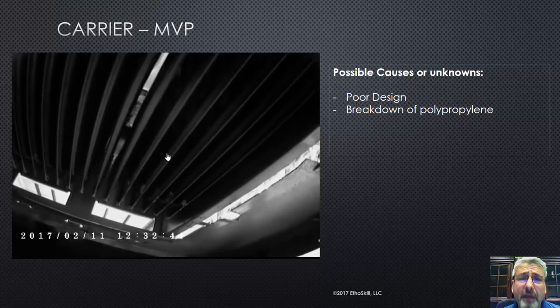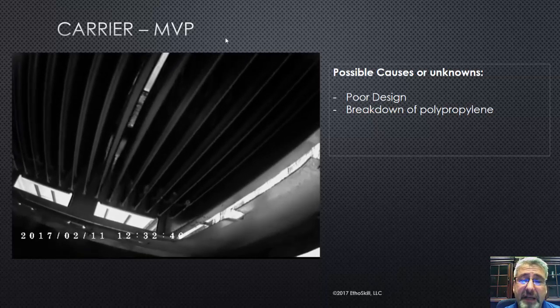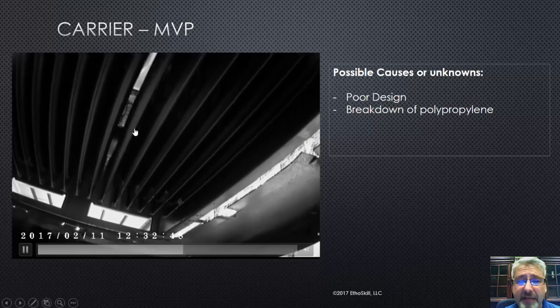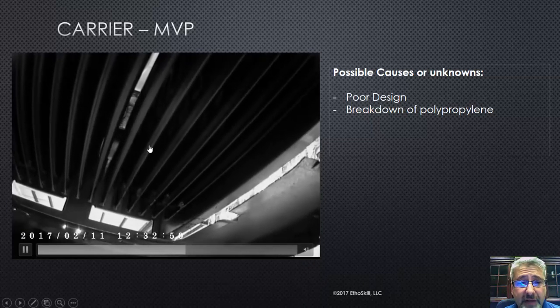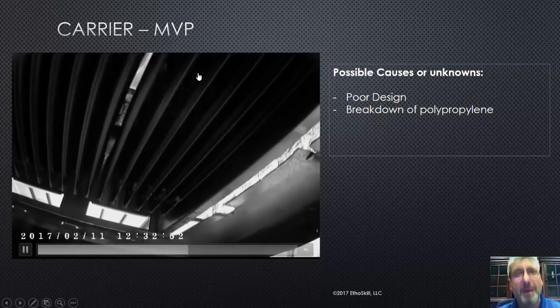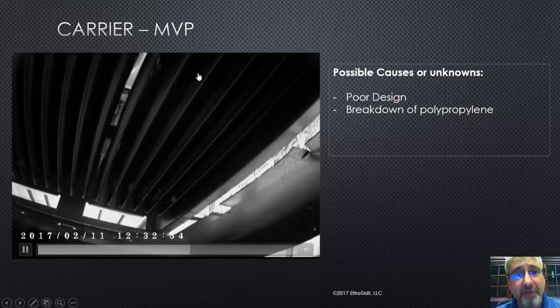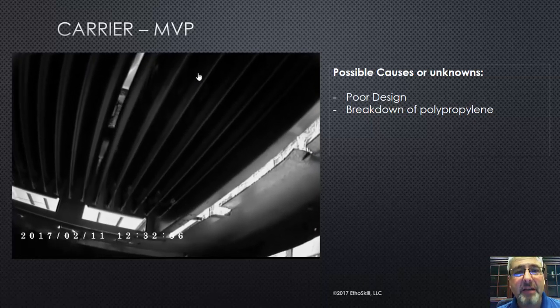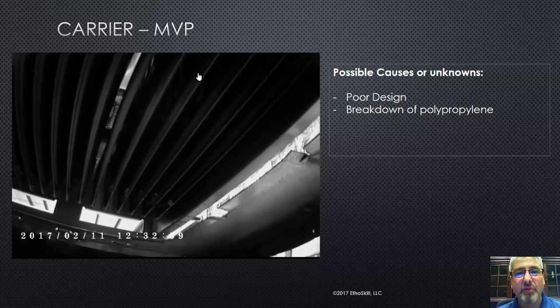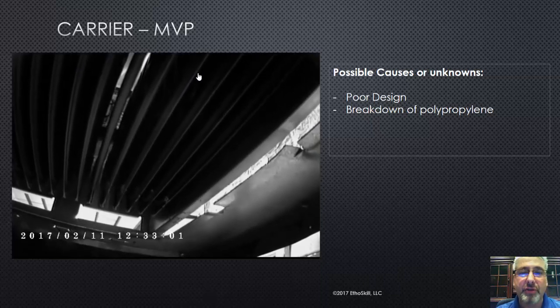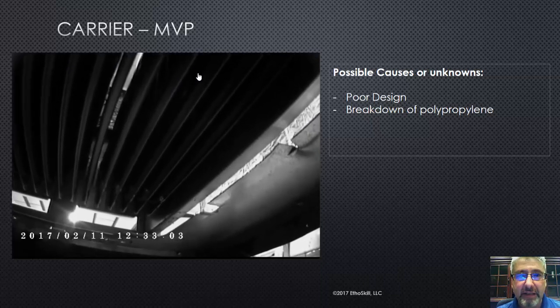Now, the condensate that develops inside of a condensing gas secondary, this is a condensing gas furnace. You have condensation that forms in here, and then that condensation travels to the front of that furnace into a collector box, and then there's a small black drain hose. It looks like corrugated drain hose that'll go over to a drain trap, and that's how that condensate leaves the furnace.